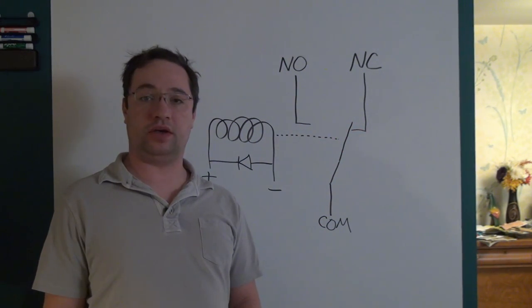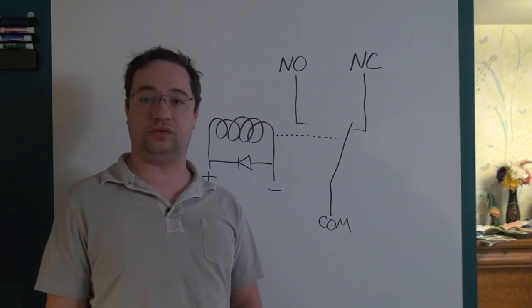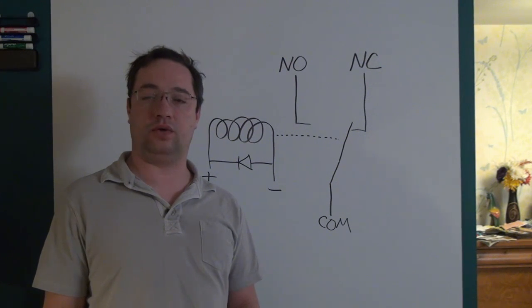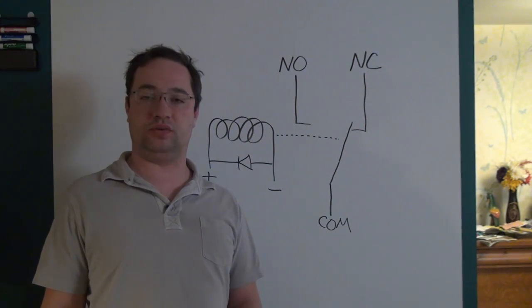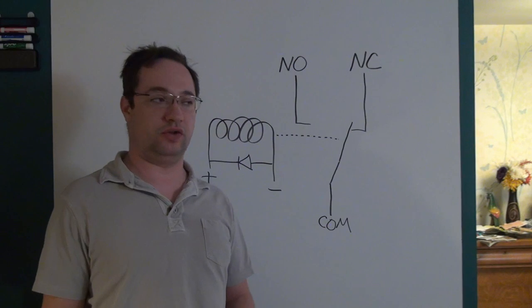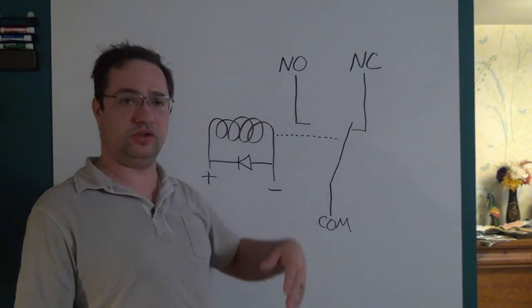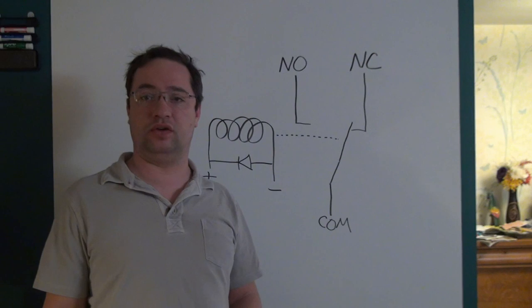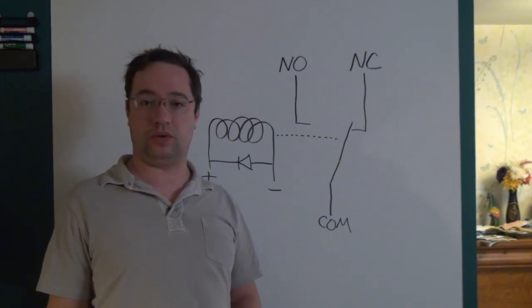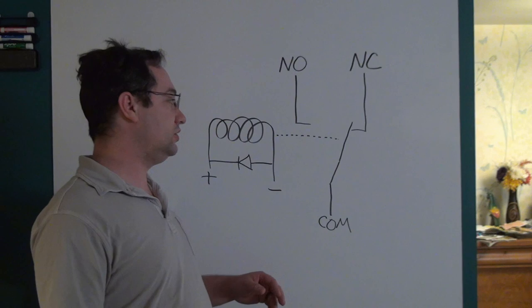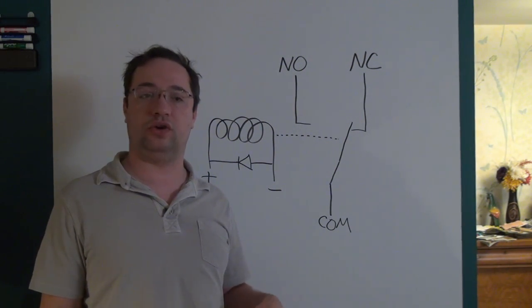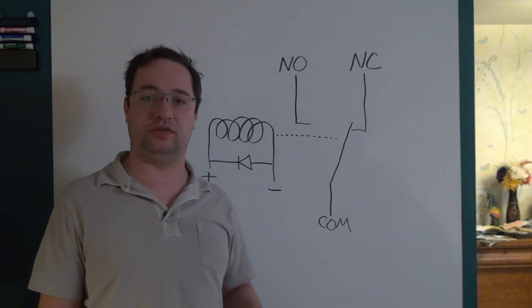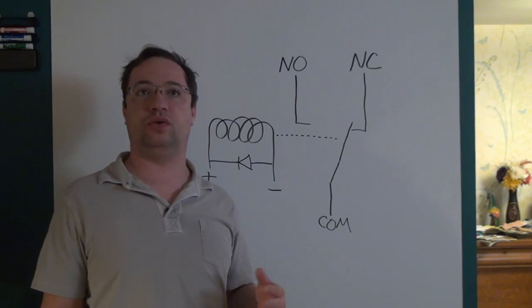To further complicate things, some relays will have a rating for a resistive load and some for an inductive load. The current rating for an inductive load will be much lower than for a resistive load. A resistive load is the simplest to switch because it doesn't have any kind of inrush or inductive effects.